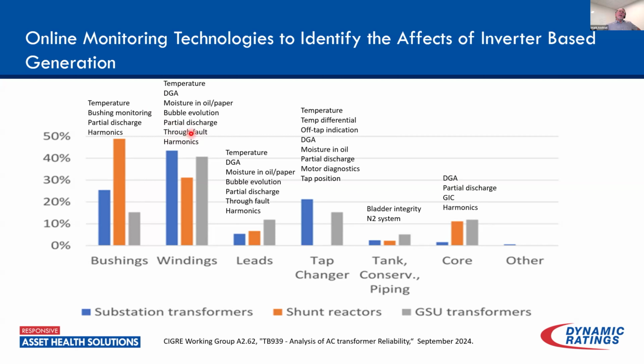And then, lastly, since faults can be a significant problem, monitoring fault activity on the transformer can give us an indication of mechanical health, but also of the harmonics that are present on that system. When it comes to the leads, we're looking at the same thing that happens with the windings. Tap changers are those other technologies. Most GSUs don't really have a tap changer. So, how often this applies to renewables, but if you do have a tap changer, there's definitely monitoring in place that can do that.